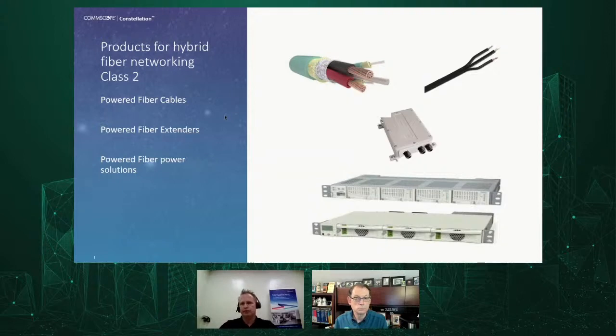When we're talking hybrid fiber cable, you need some means to convert the Class 2 power into usable power at the remote end, most commonly PoE power. So a powered fiber extender receives the hybrid fiber cable and splits it into the power section and the fiber section. An example here is a Commscope extender with cable termination and cable management built into an outdoor enclosure.